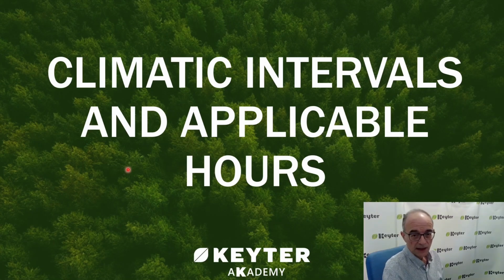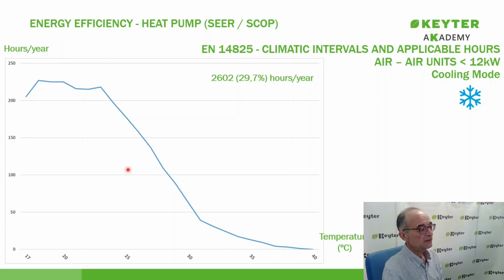What are those climate scenarios, those intervals? Well, there are several, all of them defined by the 14.825 standard. The first one we find would be for air-to-air units of less than 12 kilowatts operating in cooling mode. Here, based on the outdoor temperature, it is defined how many hours per year these outdoor temperatures occur. It's a histogram, and we see that not all the hours of the year are used, which are 8,760, I think, but rather only 29.7% of the hours are used. Of course, that's for operation in cooling mode.